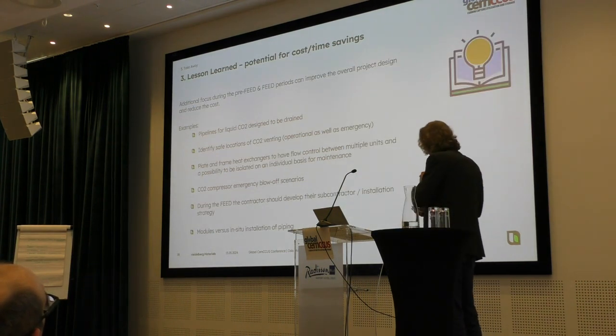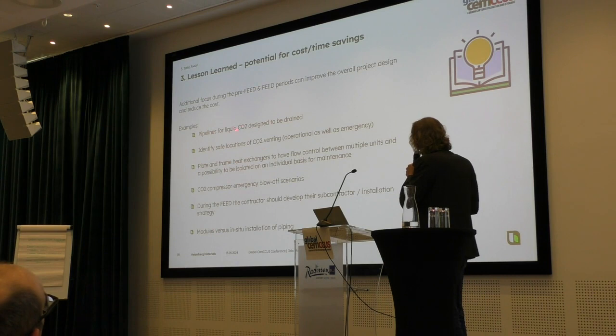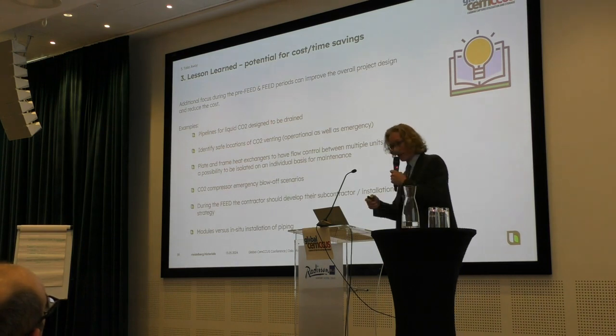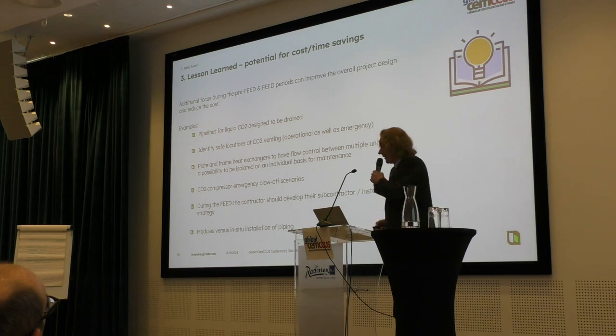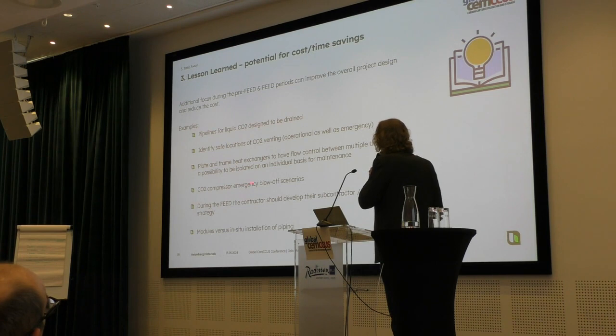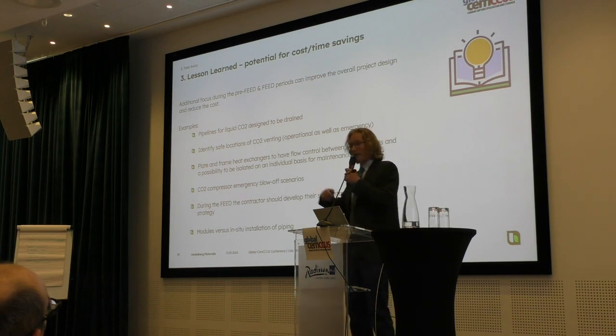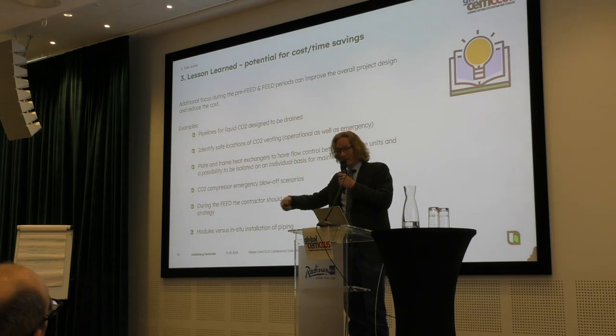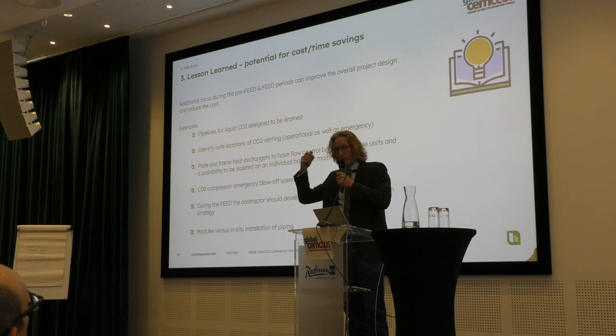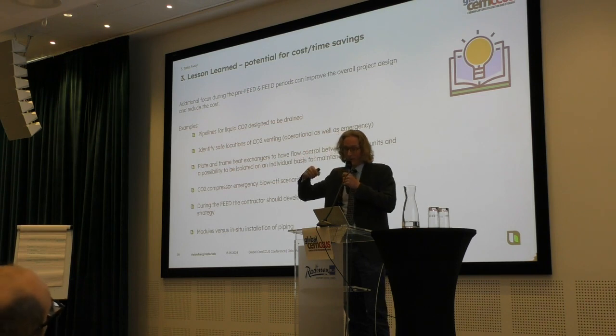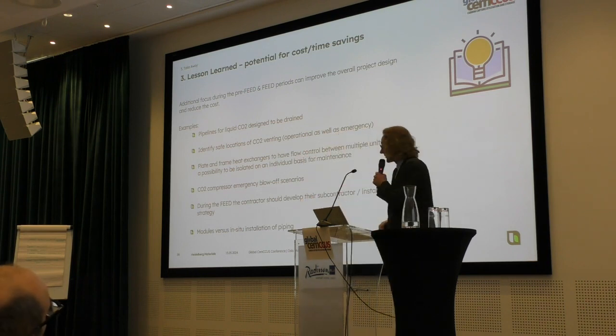Other things to consider in engineering: pipelines for liquid CO2 should be designed so they can be drained, otherwise you'll have problems. CO2 venting, CO2 compressor blow-off scenarios — every time you need to get rid of some CO2, blow off something, you need to think about where to do it from the beginning, not later in the project.